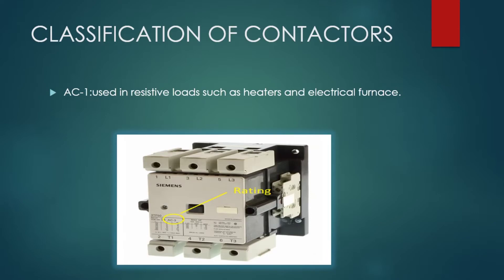The first category is the AC1 contactor. The AC1 contactor is widely used in industrial applications such as resistive loads, heaters, and electrical furnaces. Non-inductive or slightly inductive loads are included, which means the power factor of the load lies between 0.95 and 1.